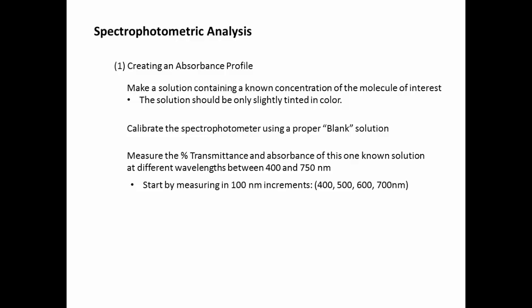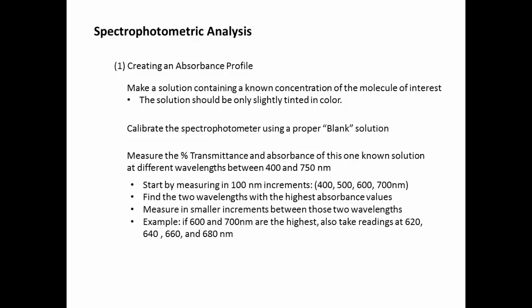Start by measuring in 100 nanometer increments. Start at 400, then 500, 600, and 700. Find the two wavelengths with the highest absorbance values. For example, if 600 and 700 are the highest absorbance values, you want to see if there's even higher values in between, so you'll also take additional readings at 620, 640, 660, and 680.